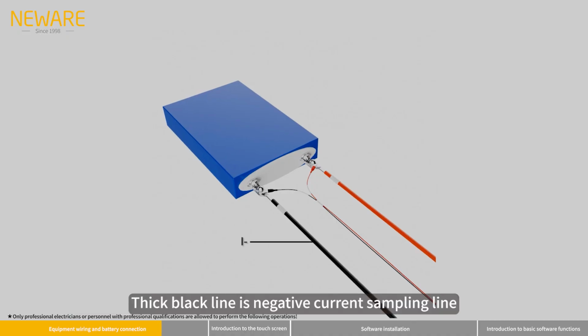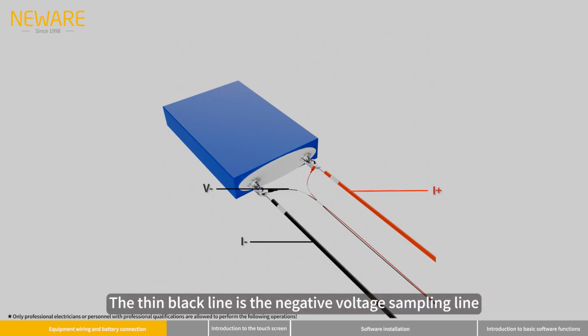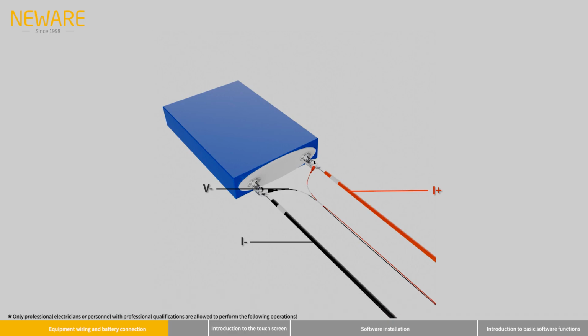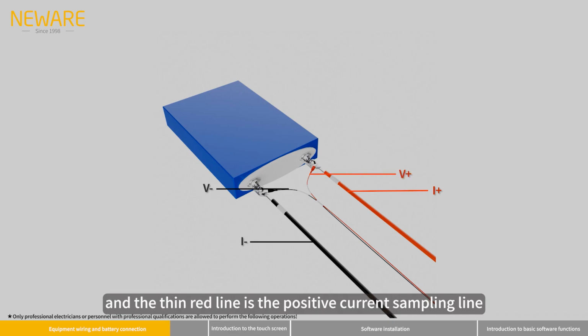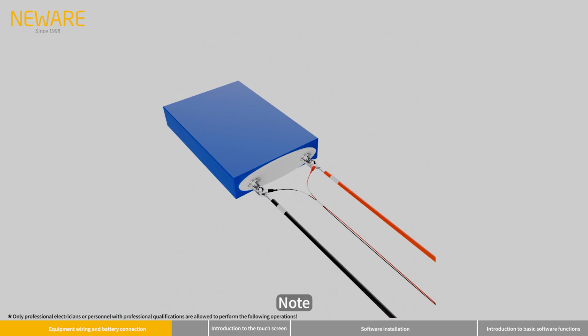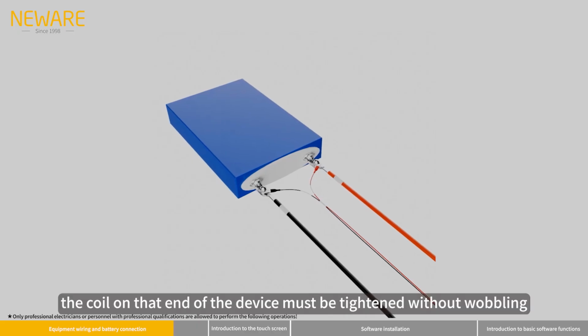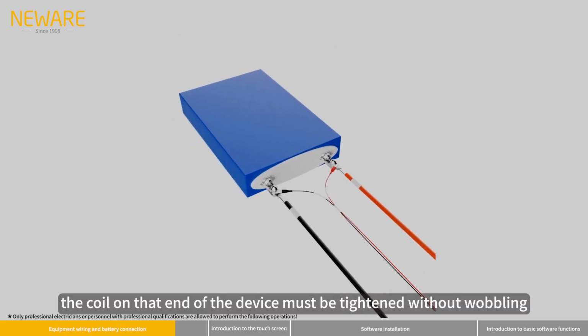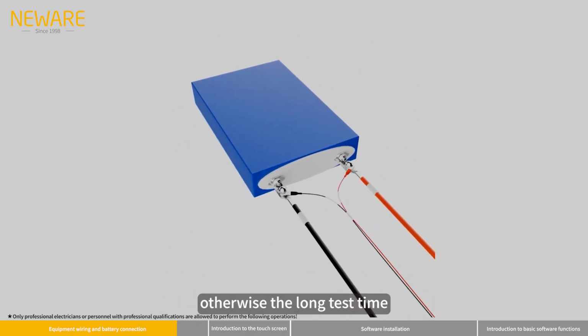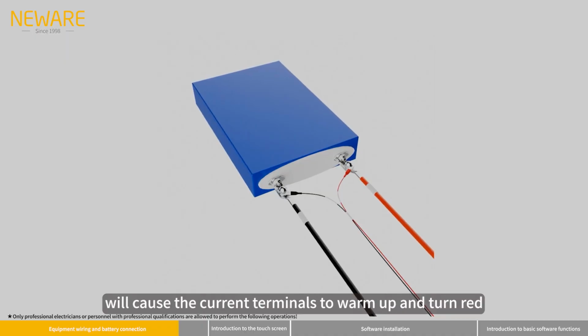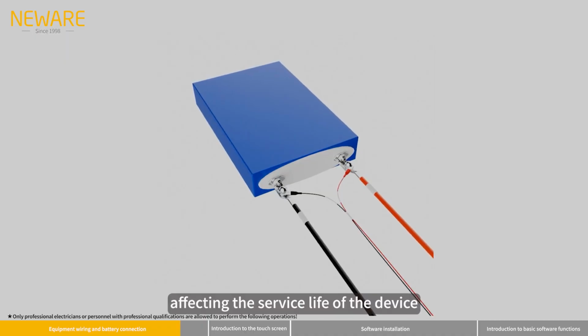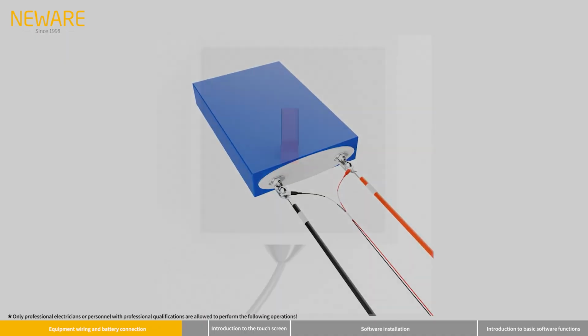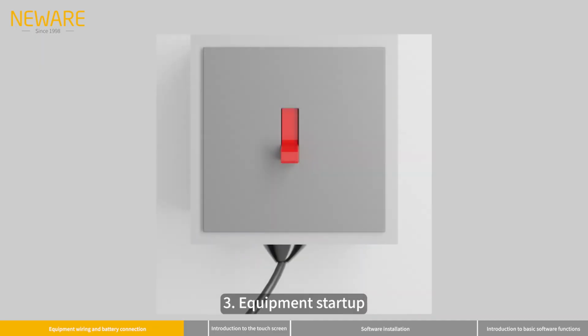Thick black line is negative current sampling line. Thick red line is positive current sampling line. The thin black line is the negative voltage sampling line, and the thin red line is the positive voltage sampling line. Note: when connecting the battery, the coil on that end of the device must be tightened without wobbling, otherwise the long test time will cause the current terminals to warm up and turn red, affecting the service life of the device.